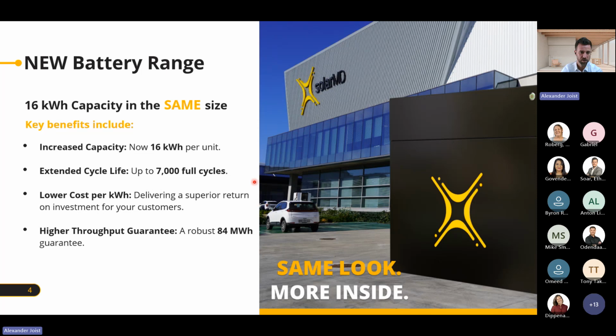Our max charge power went from 1C to 0.5C, for 2-hour systems, which is 99% of the use case anyway. So to summarize, the 16 kilowatt hour capacity is exactly the same size as before, same look, just more inside. This is throughout the whole range, changed from 14.3 to 16 kilowatt hours. So we have 10% more capacity, extended lifetime with 7,000 cycles, and with more capacity in the same housing, a lower cost on the product build, so a lower cost per kilowatt hour. We were able to have more capacity and a lower price per kilowatt hour in the whole battery, and with that also a higher throughput guarantee of 84 megawatt hours of energy throughput. Before it was 60 megawatt hours, so we now have 24 megawatt hours more guaranteed capacity we can use in a battery.